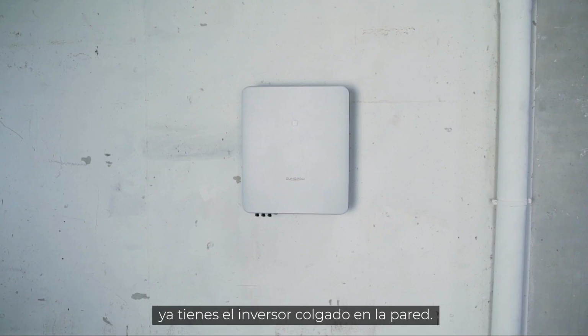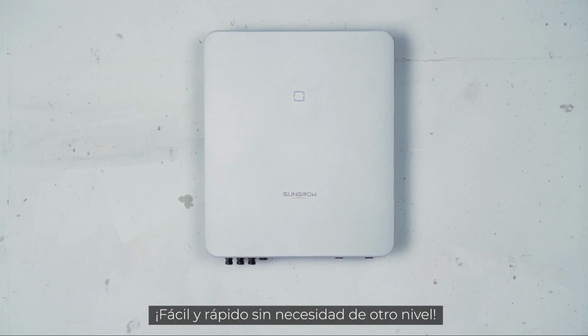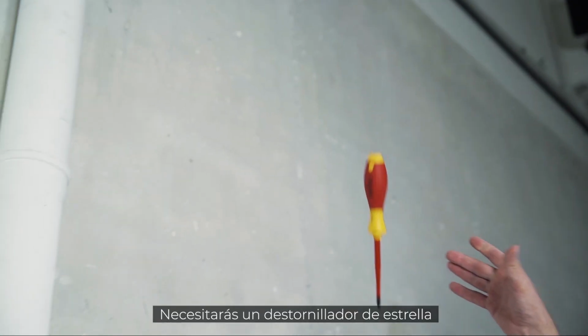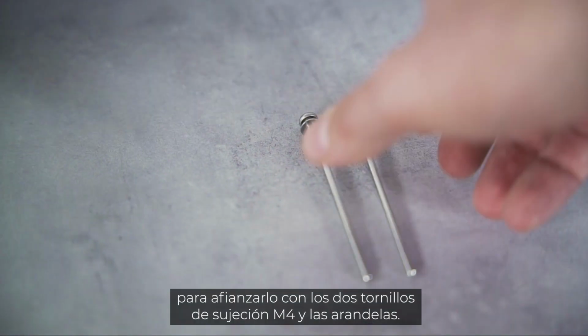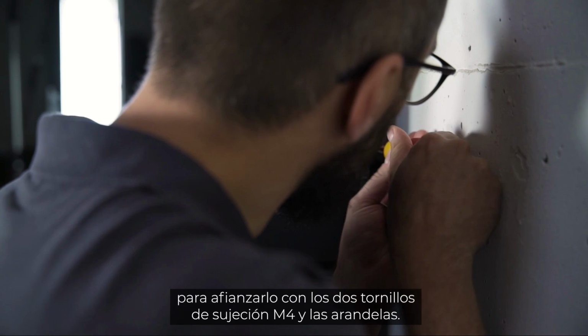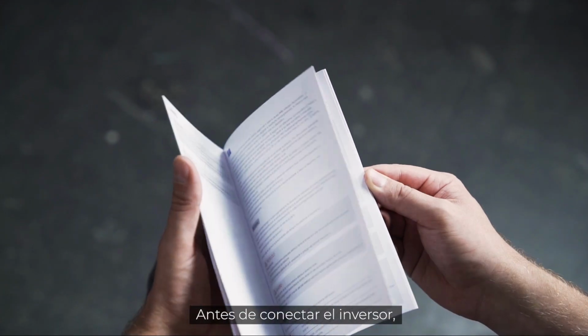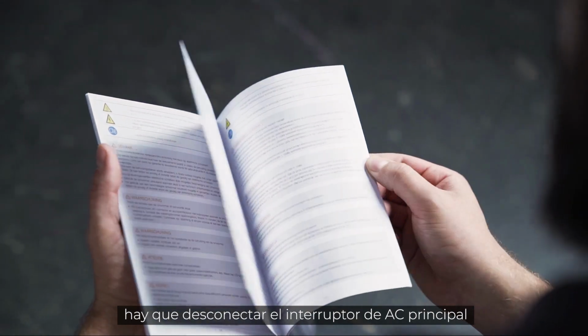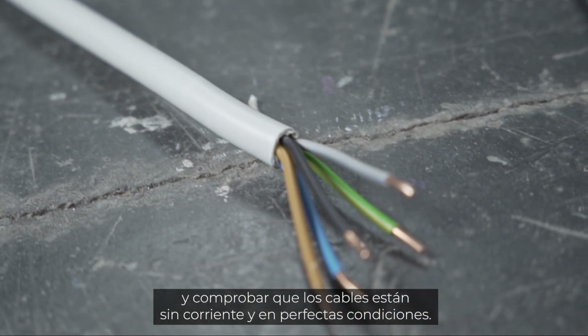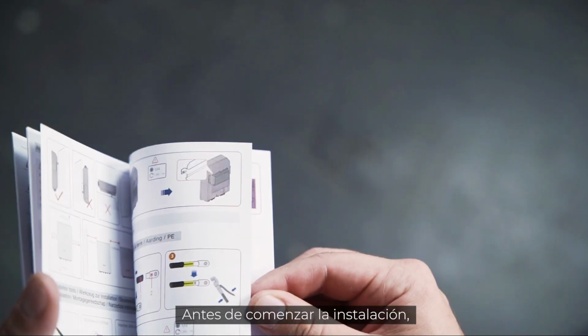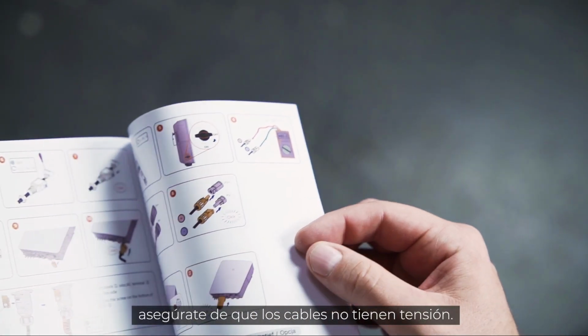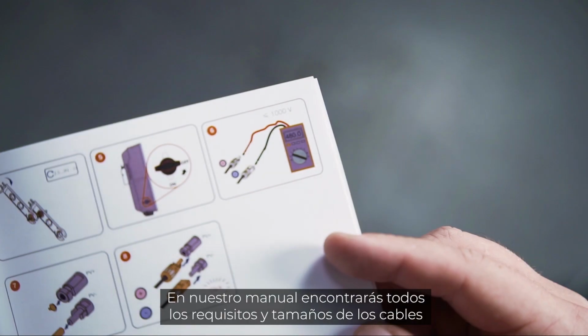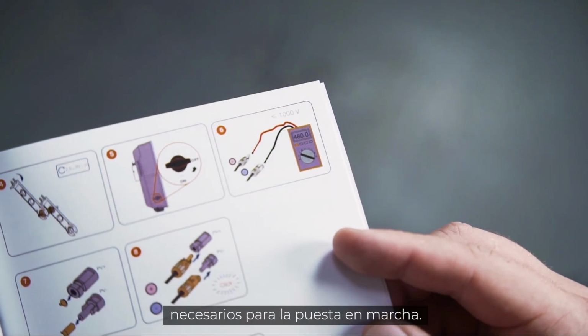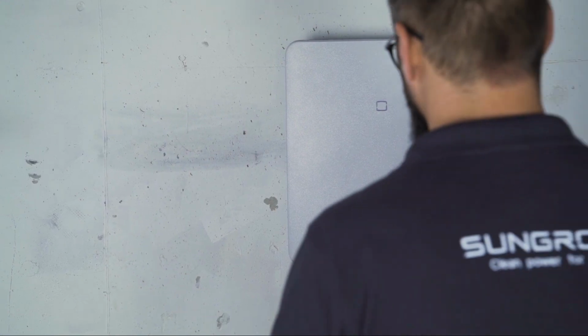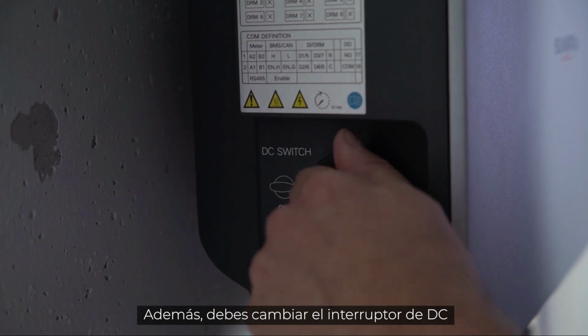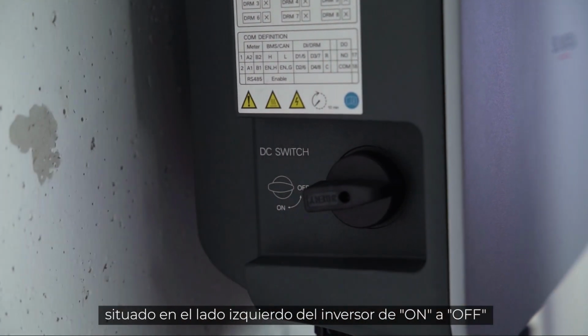Et voilà! The inverter hangs on the wall, quick and easy, without the need of an extra spirit level. For the lift-out protection, you need a cross screwdriver to fix the two M4 fixing screws and washers. Before the inverter can be connected, the AC home circuit breaker must be disconnected, the cables must be de-energized and in perfect condition. Before installation, make sure by measuring that the cables are really voltage-free. You will find all cable requirements and wire sizes necessary for commissioning in our manual. Furthermore, you have to set the DC switch on the left side of the inverter from on to off.